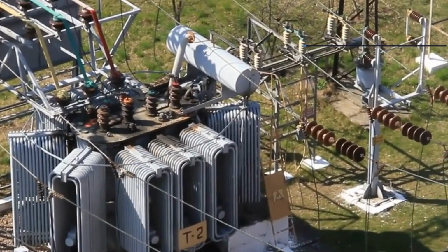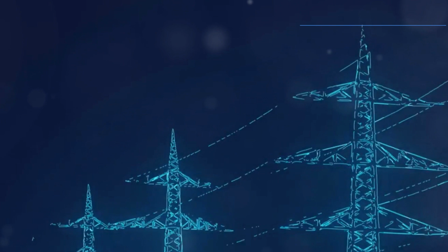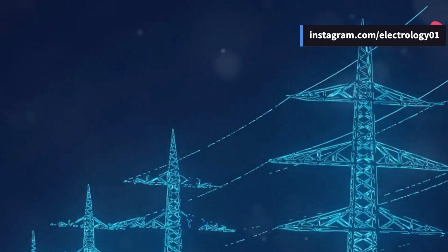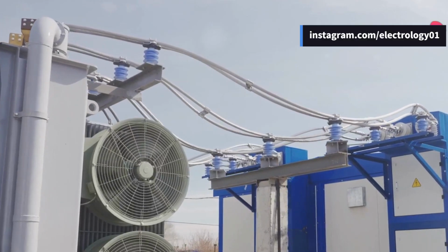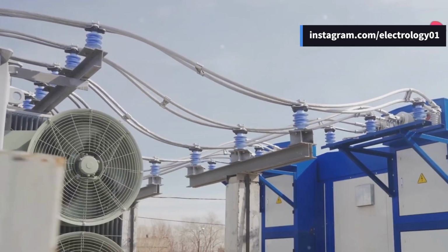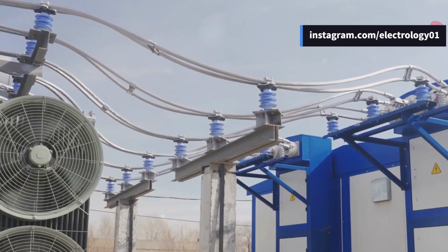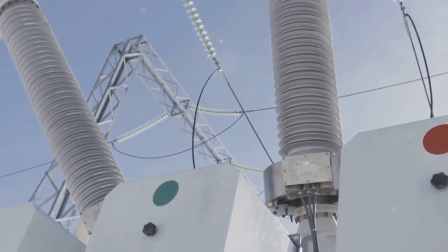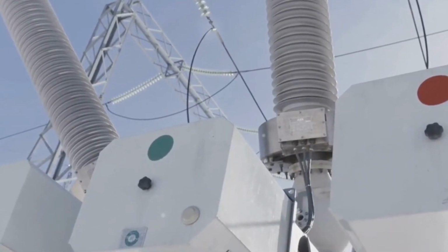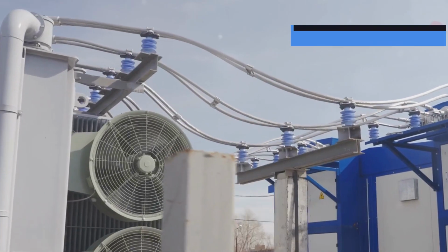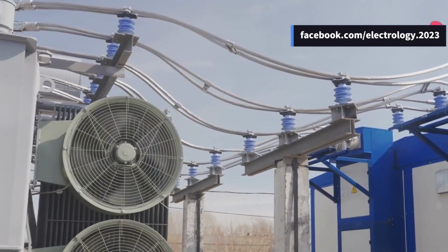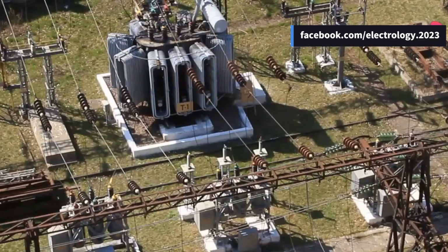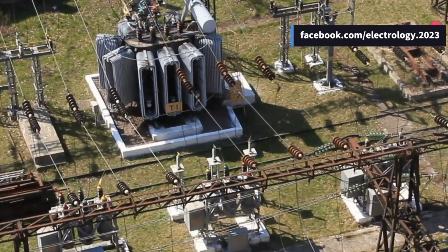Availability. If one transformer needs maintenance, the others can handle the load, minimizing downtime. Reliability. If a transformer fails, the remaining ones can share the load, potentially preventing a complete power outage. Flexibility. Adding or removing transformers in parallel allows you to easily adjust to changing power demands. This avoids the unnecessary expense of a giant transformer for future needs or inefficient operation with a large transformer for a smaller current load.